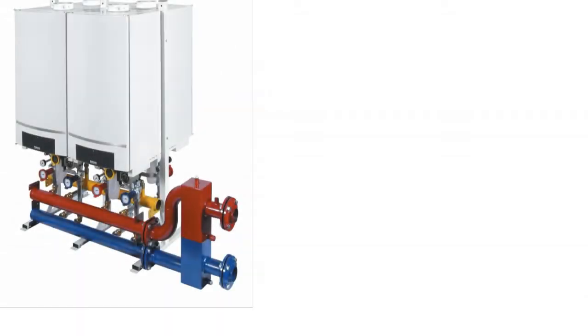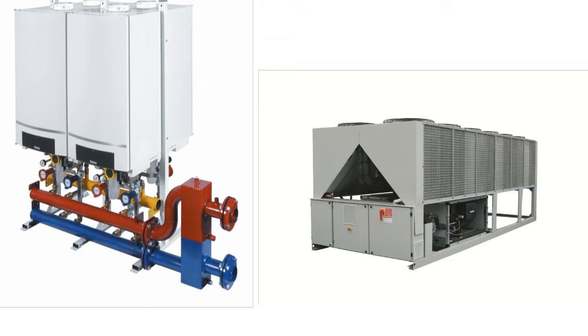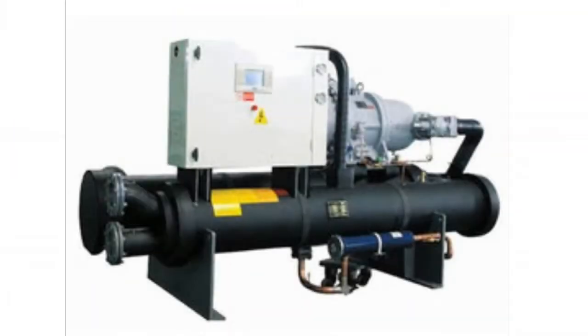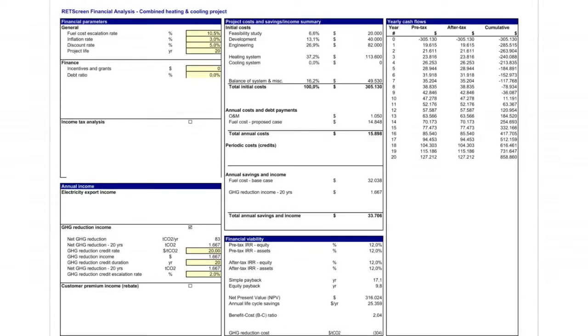Two options for the HVAC and auxiliary system were compared. Option 1, gas boiler for heating and air-cooled chiller for cooling. Option 2, ground source heat pump covering both cooling and heating loads plus PV. Inflation rate was assumed to be 3%, and the fuel cost escalation rate was based on a 10-year average increase, as suggested by the project requirements. A period of 20 years was chosen for the analysis, representing the approximate lifetime of HVAC equipment.